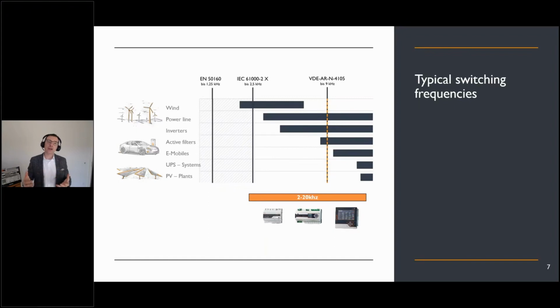These requirements are also changing. So in the meantime, if I produce a new product, the higher harmonics are checked as a sink. If I provide a product, the product itself is a source of issues and at the same time a sink of issues in these high frequency ranges. In the past, it was not addressed, and this is the main issue.